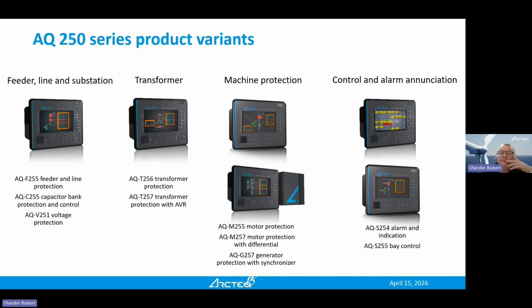this type of functionality. Then we have an alarm annunciator. This one is starting to be quite a unique device. Today we have full 61850 with GOOSE, so you can collect alarms in this device with communication or with hard wiring. You can get more than 100 signals into this device with hardwire, and then you can connect with GOOSE, of course, as much as possible. And then a very flexible display, so you can decide how many you want to show and so on. And then we also have bay control devices and things like that.